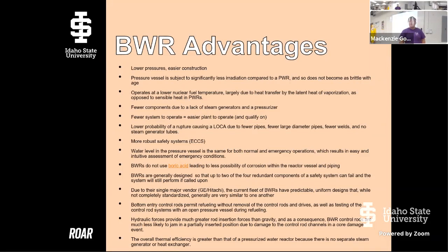One nice thing about having the control rods at the bottom is that we don't have to take the control rods or drive out of the core when we need to refuel. In a pressurized water reactor, you open the top of the reactor and have to pull out the control rod drives and rods to get at the fuel, which creates unique criticality challenges and safety issues, because the control rods being in the core are what prevent us from having a reactor when we don't want one—they prevent that critical reaction. With bottom entry, they get to stay in, and we can access the fuel from the top just by moving the steam separator out of the way.